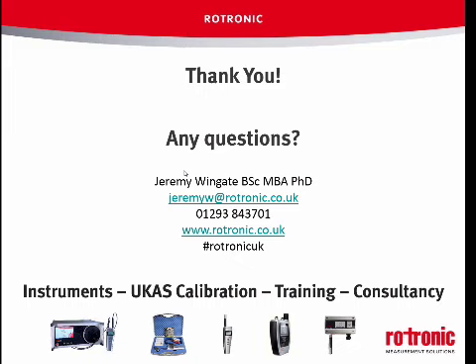Yeah, it's a difficult one. If you were to put them literally side by side in a reasonably stable room, you'd hope a 2% accuracy sensor would read within 2%. You'd want them to be reasonable. But there are so many uncertainties going on. Me breathing on these, one's going to get more humid than the other. Hopefully you wouldn't breathe on them. So you're trying to isolate as many things as possible to avoid variation.